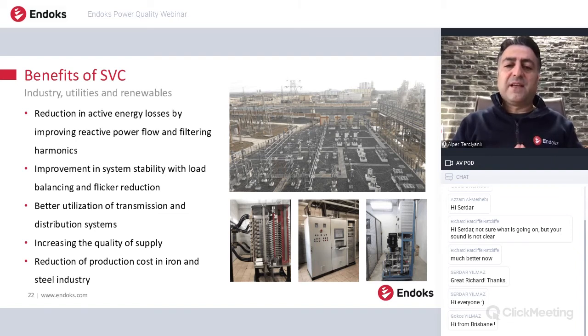According to the maximum power transfer theory, the impedance of the load and the impedance of the system should be matched. So these SVCs are being used to make these impedances matching by eliminating all imbalances and reactive power in the system, and making the voltage very smooth and on the ideal case, and transferring the maximum power from grid to the load. This means that the time to have a melted steel in a shorter time, because if you transfer more power, then you can have the melted steel in a shorter time.